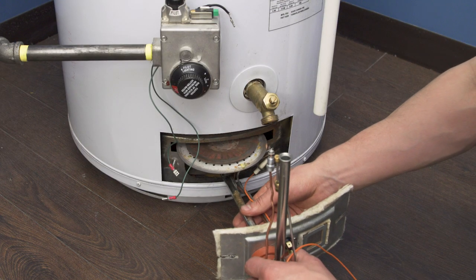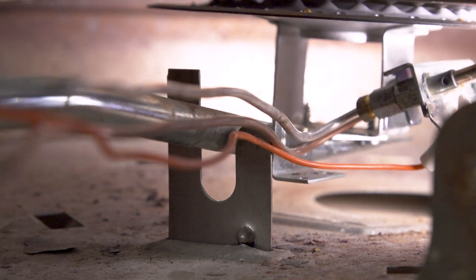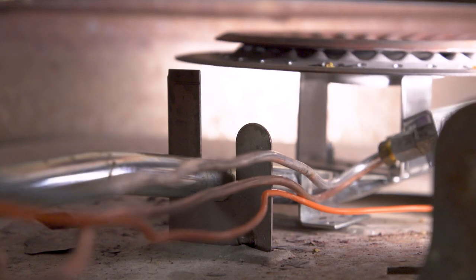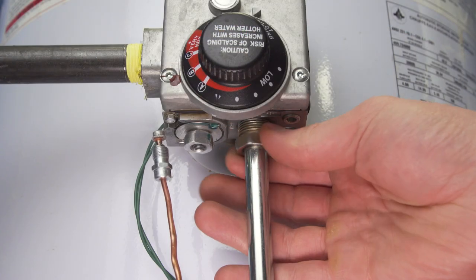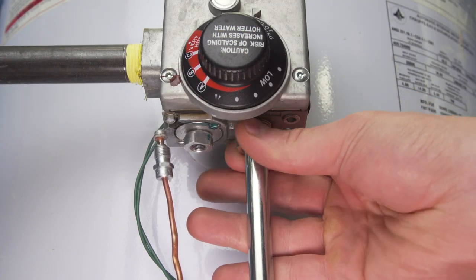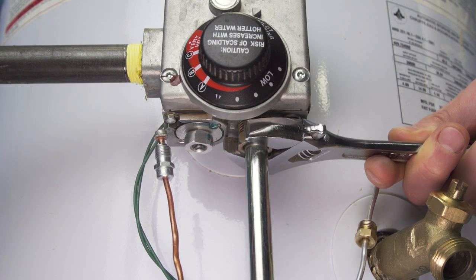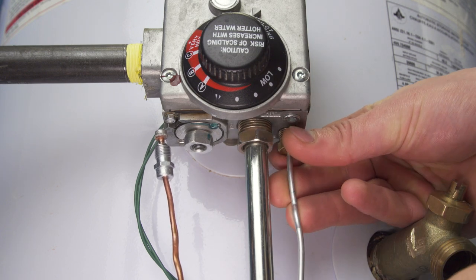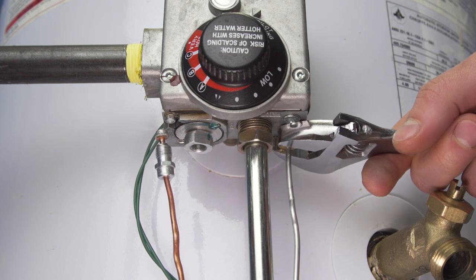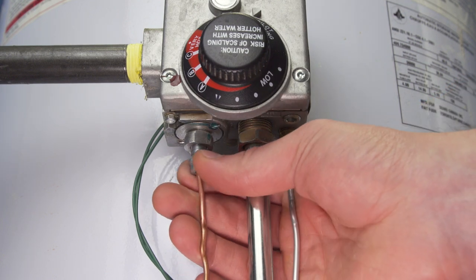Slide the burner assembly into the tank and align the tab into the bracket. Align the manifold tube into the control valve and tighten it with an adjustable wrench. Be careful not to over tighten the nut as the threads can easily strip. Now connect the pilot tube and tighten it into place. Now screw in the thermocouple.